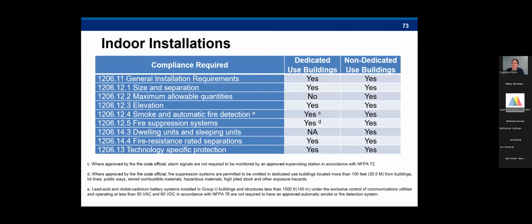So here is a chart that's provided in the code, which is a list of all the compliance that indoor installations need to meet. We have already reviewed the general installations requirement, the electrochemical protections, and the chemistry specific protection. And you can see here, when we're looking at where the project is located, that the maximum allowable quantities is not required for dedicated use buildings. So if you have a building that's only meant to be energy storage, you're not going to have that cap of 600 kilowatt hours.